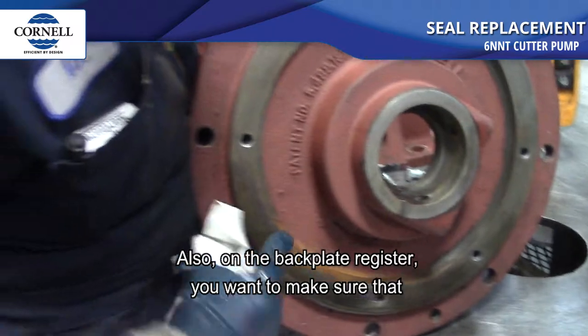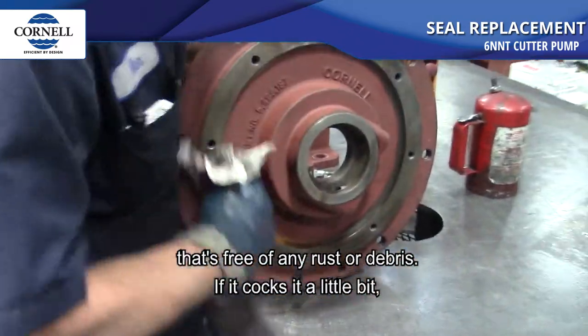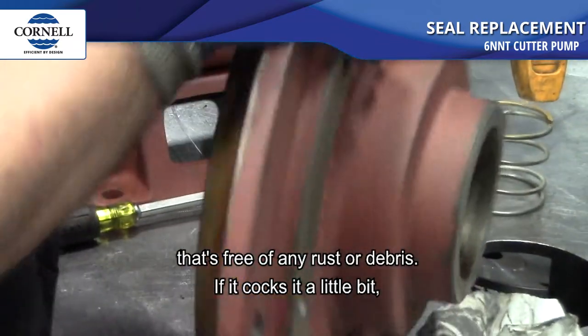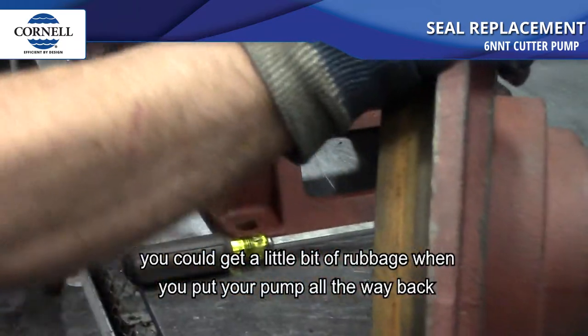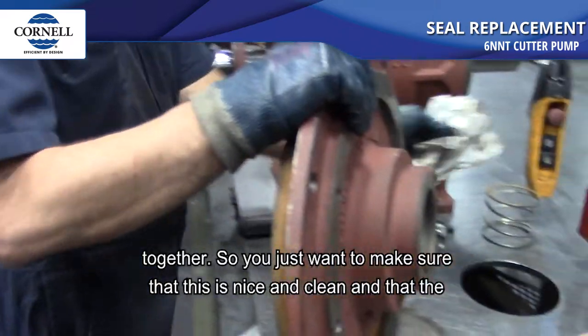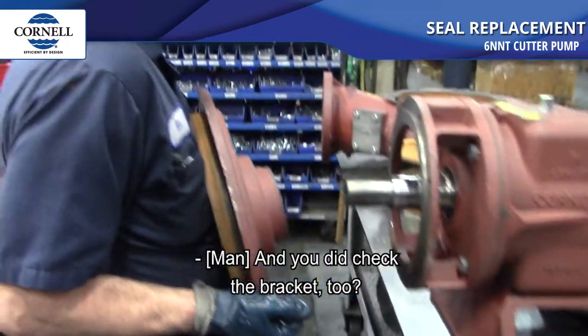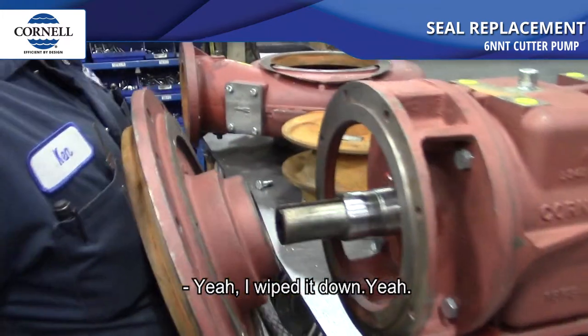Also on the backplate register, you want to make sure that's free of any rust or debris. If it cocks a little bit you can get some rubbing when you put the pump back together, so make sure the register and the face of the bracket are nice and clean. Yeah, I wiped it down. Yeah.